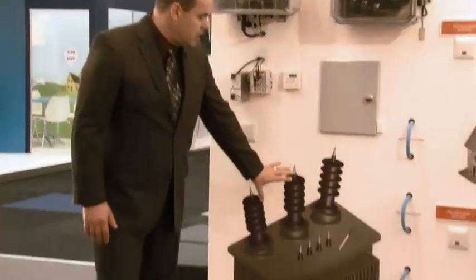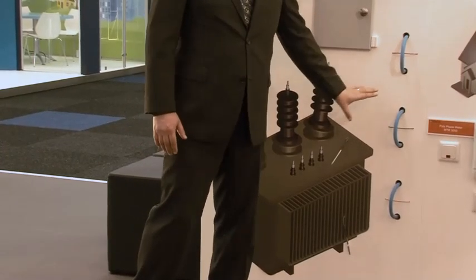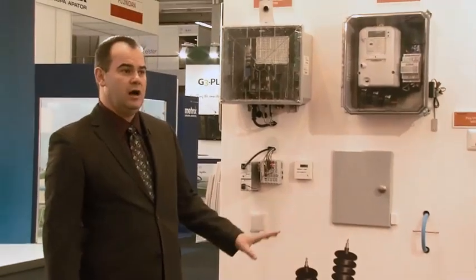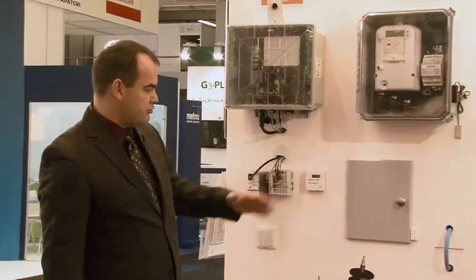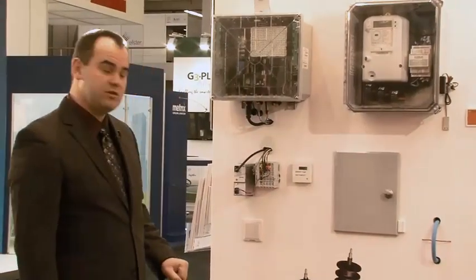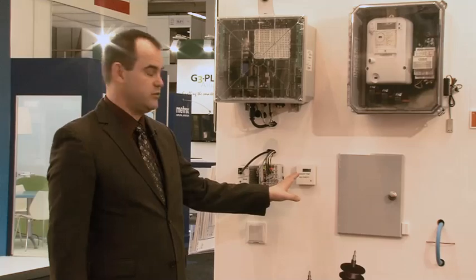We have the transformer here with three CTs monitoring the electricity flow, watching for peak load as well as any progression of load over time. We also have temperature sensors at the bottom and top of the transformer as well as an ambient temperature and a humidity sensor here.